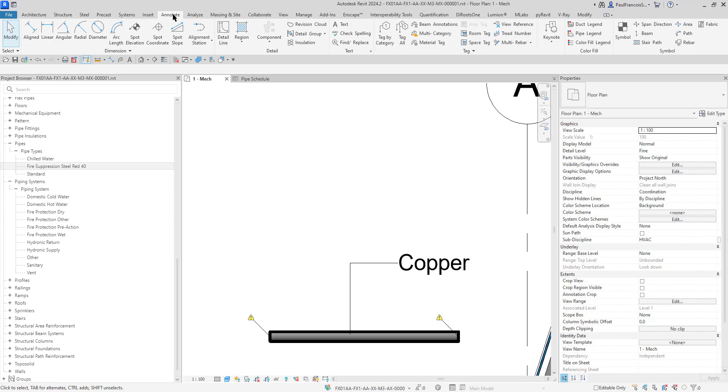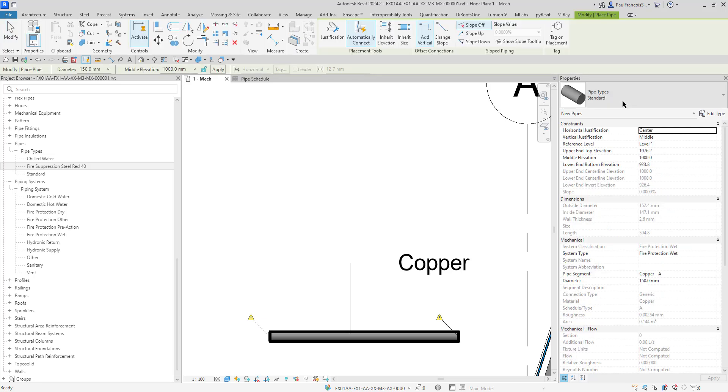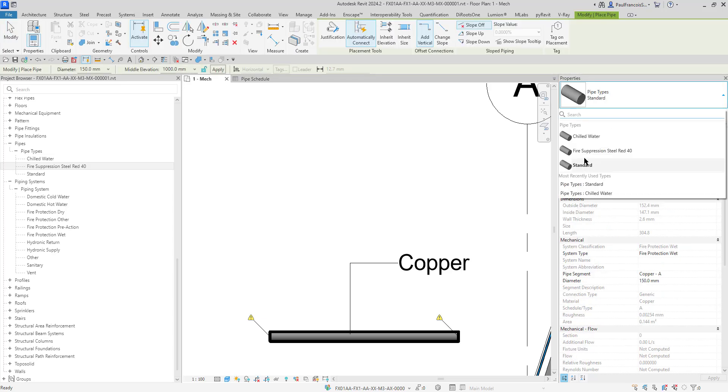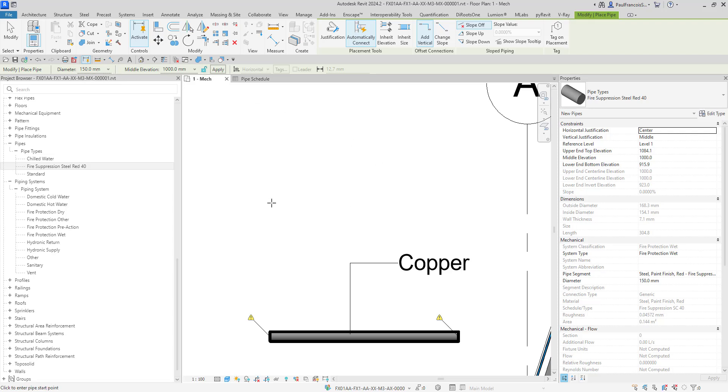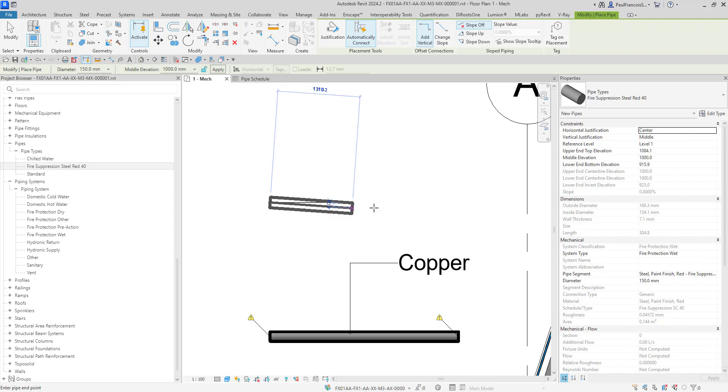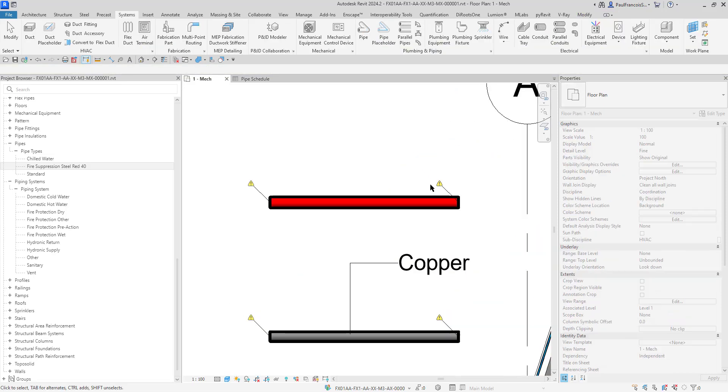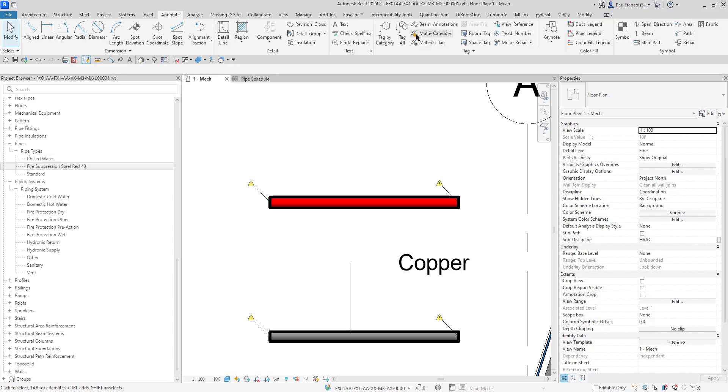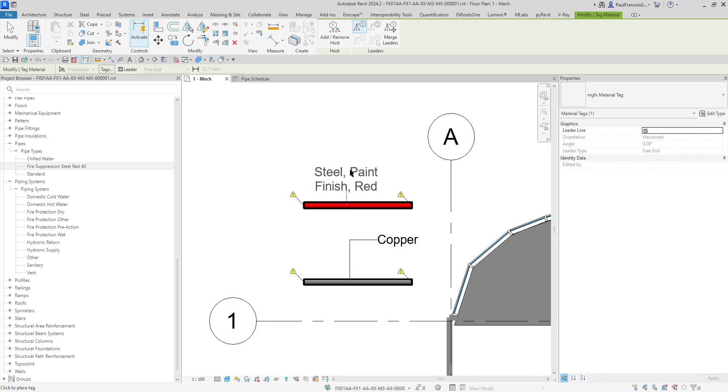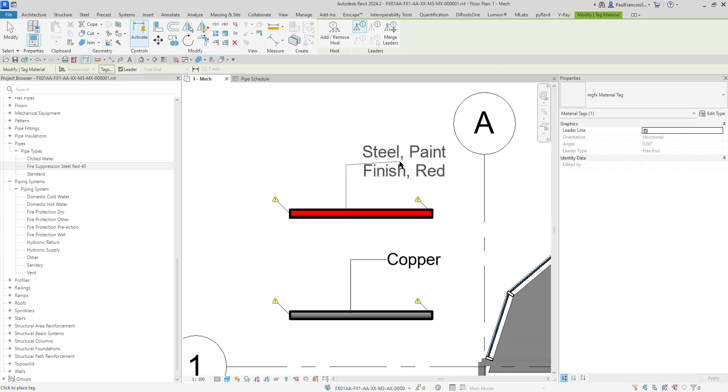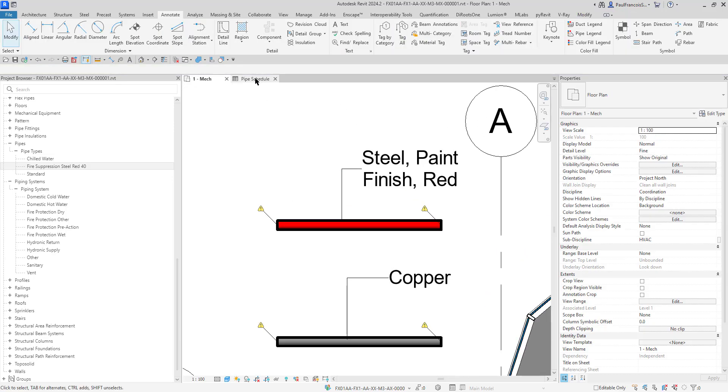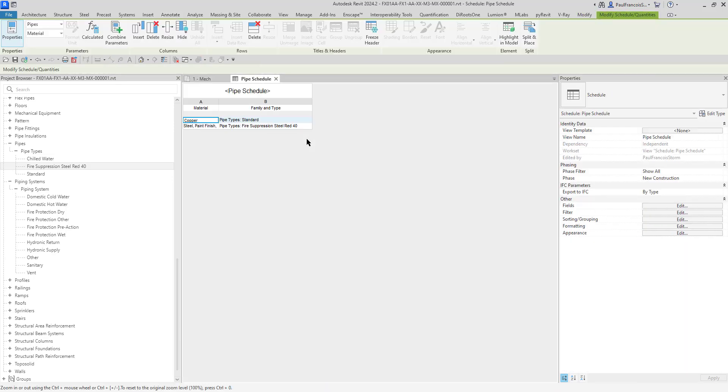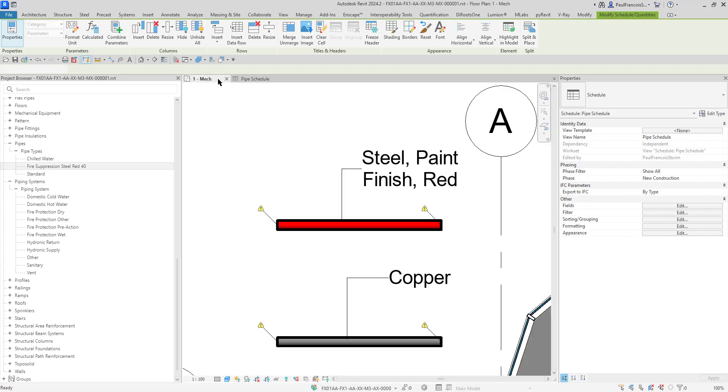Let's go and create the new pipe. There's our systems, there's our pipe. We're going to choose the pipe type to be the fire suppression type. It's going to be 150mm and 100mm. Let's draw that and see what that looks like. There you can see it immediately comes through with the correct material. If we now slap on a material tag, we can see it is actually the correct material tag. On our schedule, the pipe schedule, we can see it's the correct material. Once we get the quantities out of the schedule, we'll at least know we're ordering the correct type of material and calculate costs.